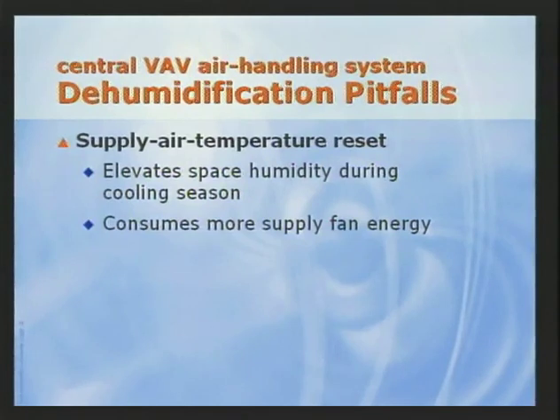It also increases the energy consumed by the supply fan, which may even negate the cooling and reheat energy saved. The second challenge is high minimum airflow settings. Each VAV terminal has a minimum airflow setting that's based on the performance limits of the diffusers or terminal, or more likely in classrooms, on the ventilation requirement of that space. In densely occupied classrooms, these minimum airflow settings must be relatively high to assure proper ventilation.